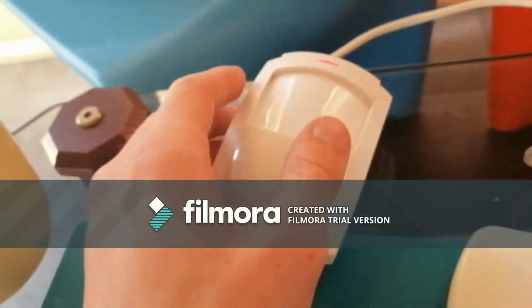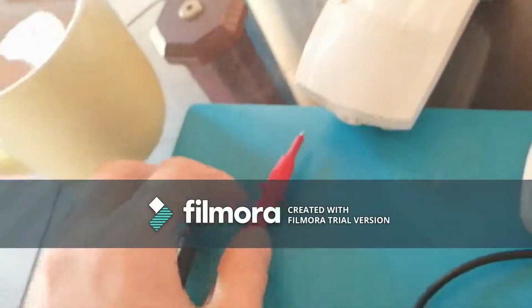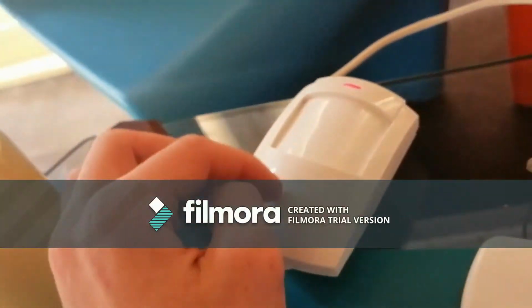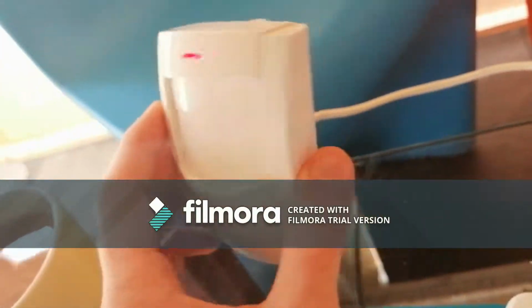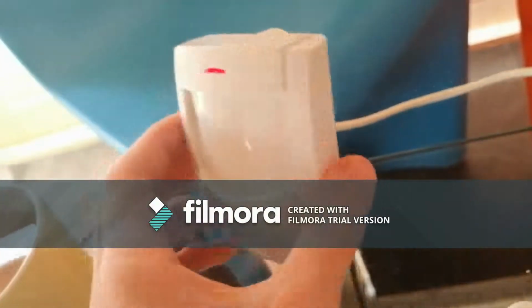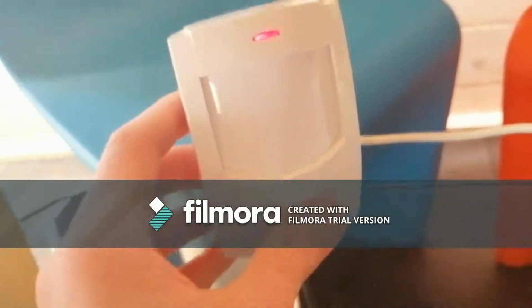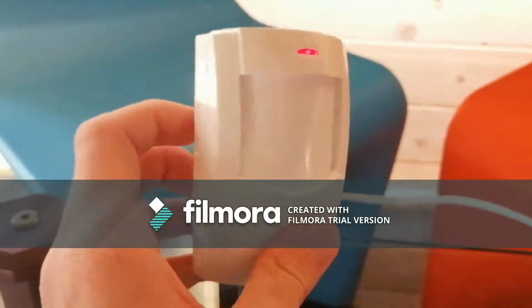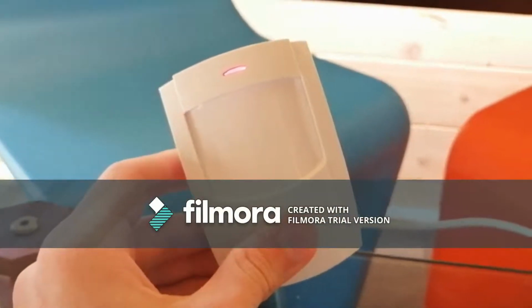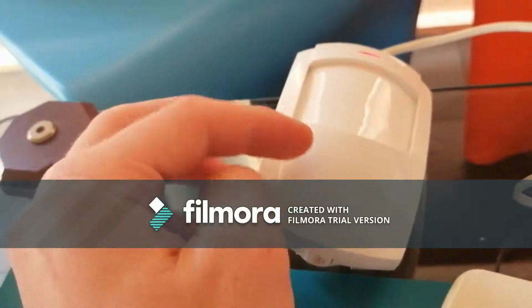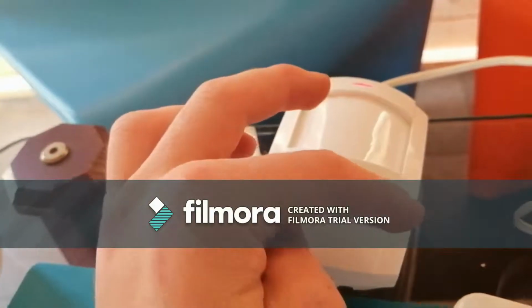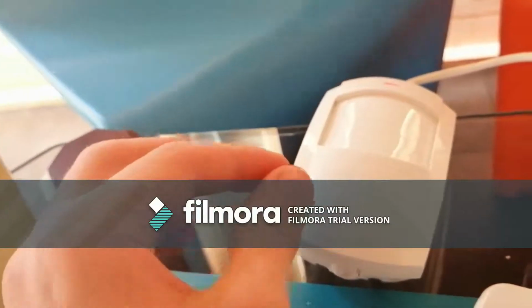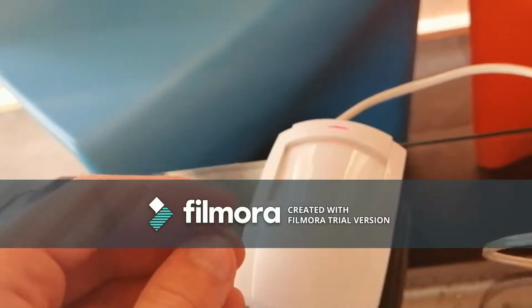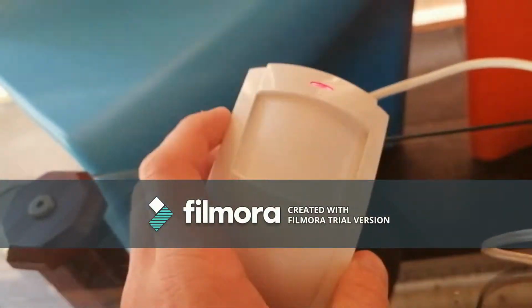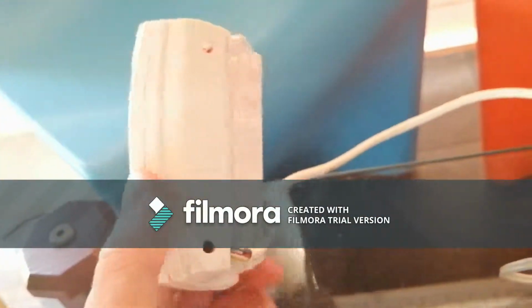So you can have a look inside, and there's usually a brand name or a model number, and if the system isn't too old, then you might still be able to get the detectors. So it's just a like-for-like replacement, which makes fixings and that easier. It is really simple to replace these, as you simply take each wire out one by one. But as you take each one out, take note of the connections and also tape them so that none of them make contact as you take it off the wall.